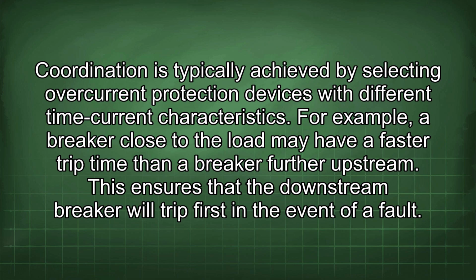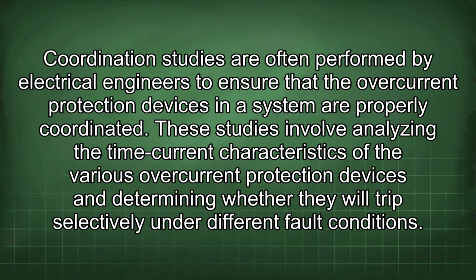Coordination is typically achieved by selecting overcurrent protection devices with different time current characteristics. For example, a breaker close to the load may have a faster trip time than a breaker further upstream. This ensures that the downstream breaker will trip first in the event of a fault. Coordination studies are often performed by electrical engineers to ensure that the overcurrent protection devices in a system are properly coordinated. These studies involve analyzing the time current characteristics of the various overcurrent protection devices and determining whether they will trip selectively under different fault conditions.